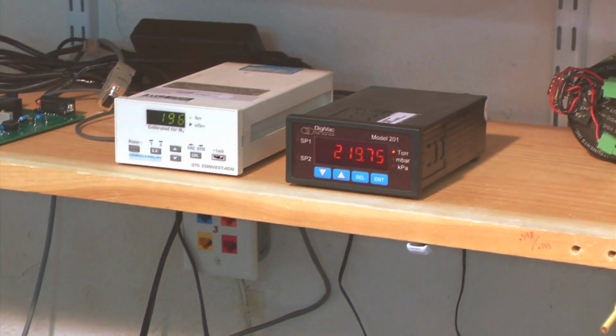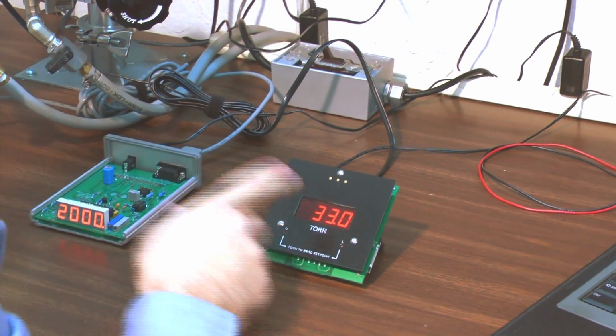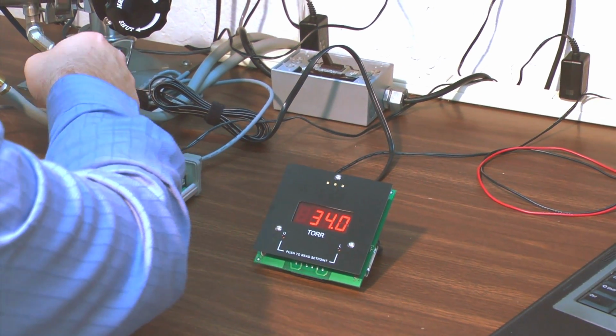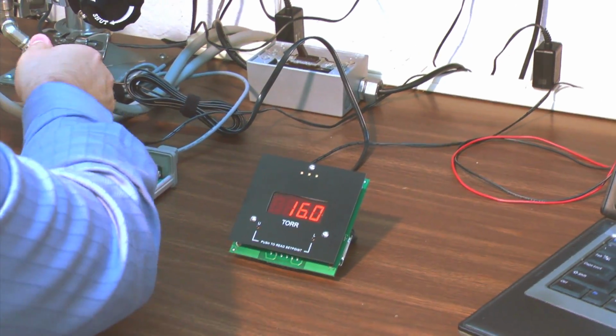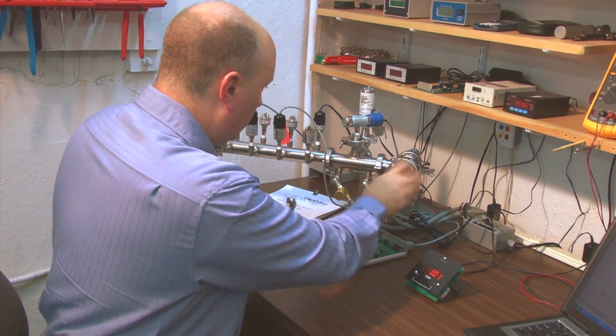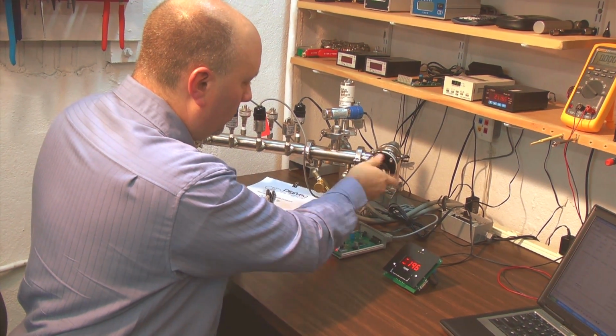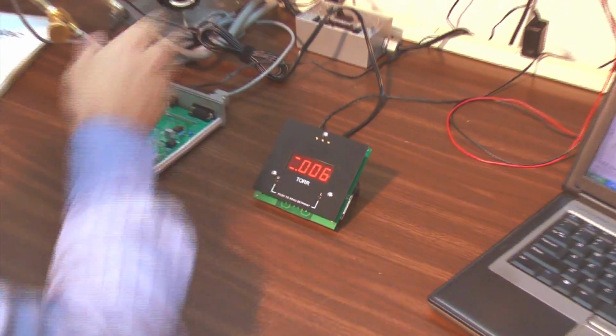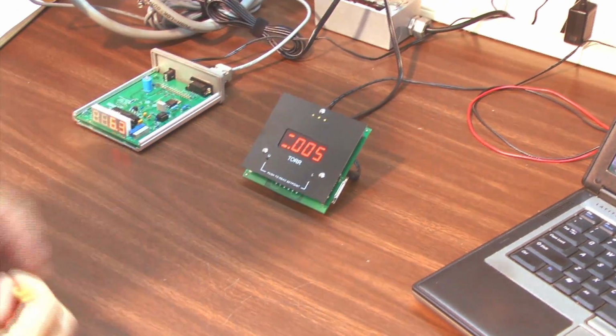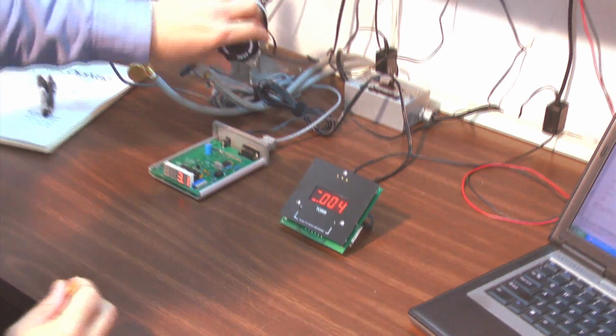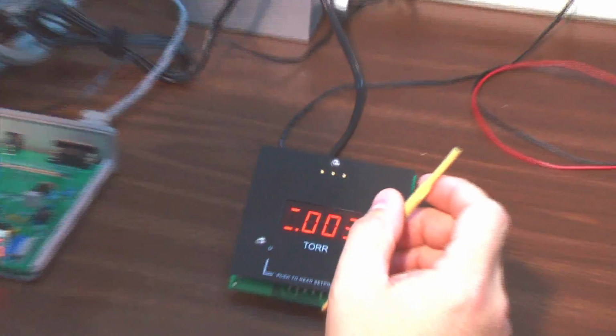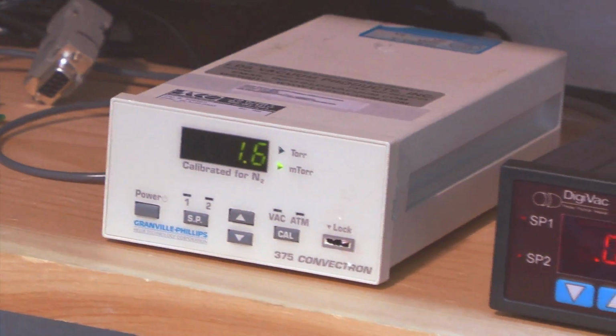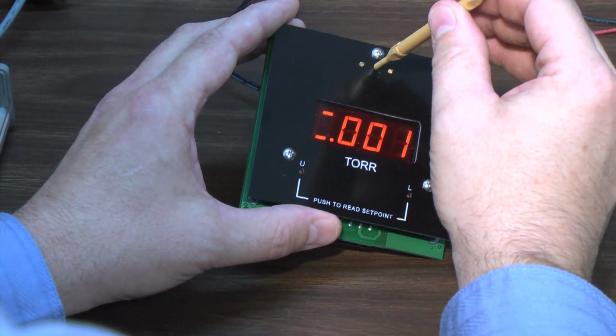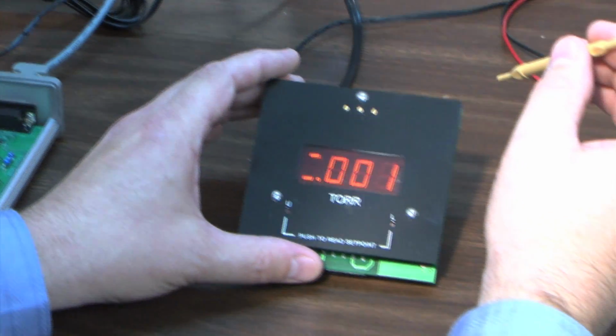219 torr on our Baratron, 200 torr on our 801W. 19.5 torr on our Baratron, 34 torr on the 801W. Looks like we'll make another correction down on the bottom end. To do that, we'll pump our system all the way back down to hard vacuum. Again, using our diffusion pump to achieve 1 millitorr or less. Wait for our system to stabilize, and we'll make a 0 correction. Convectron indicates 2.0. We would like to see 1 before we make an adjustment. Convectron indicates 1. DigiVac 801W indicates 1.